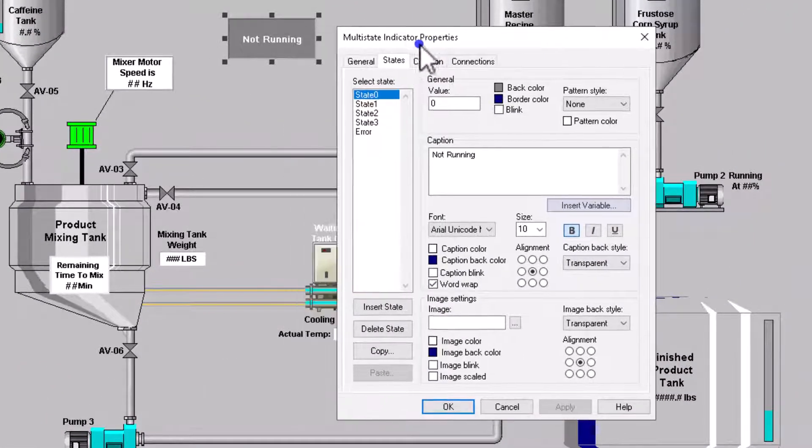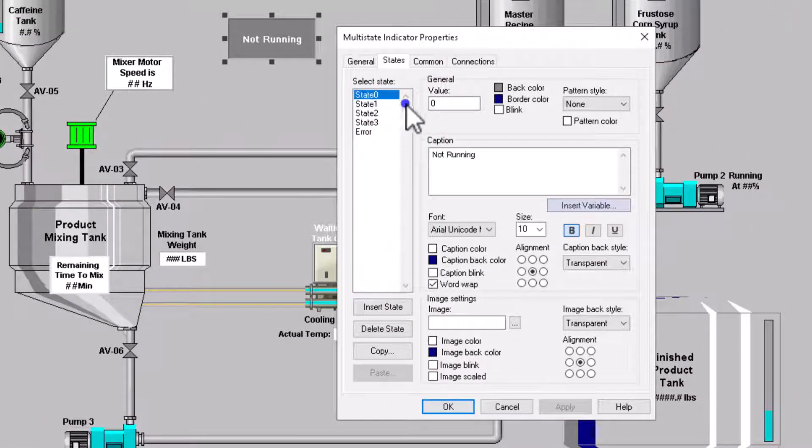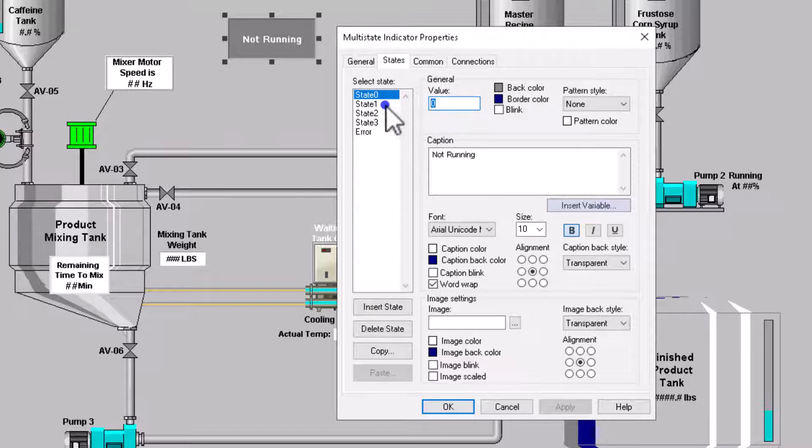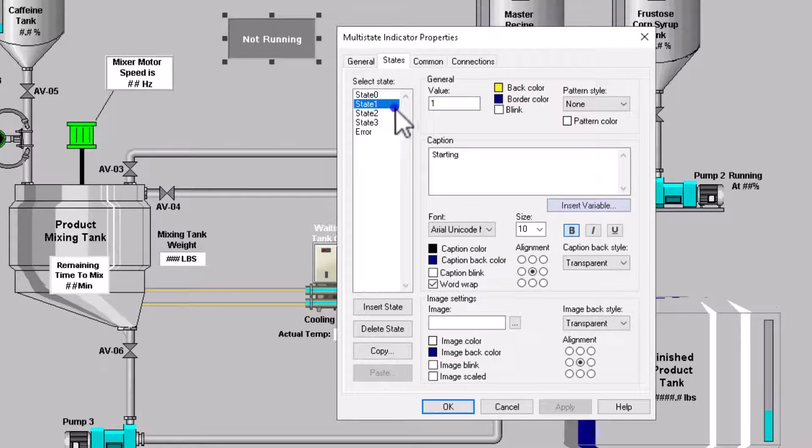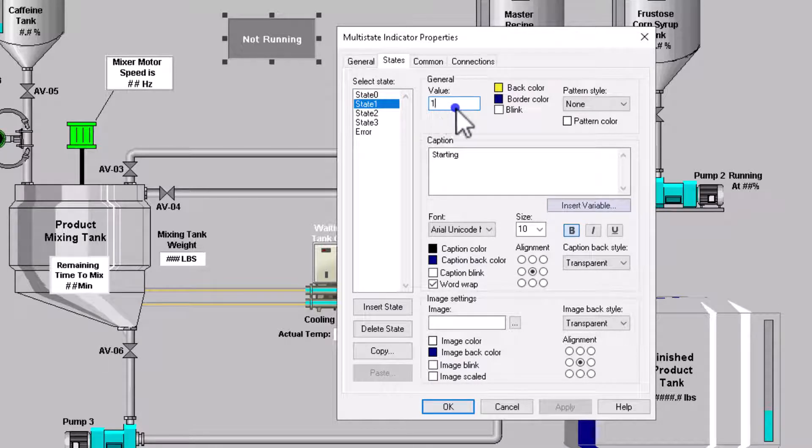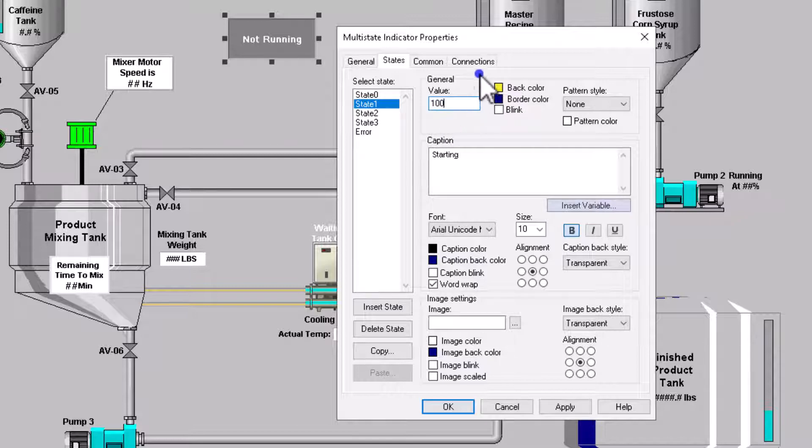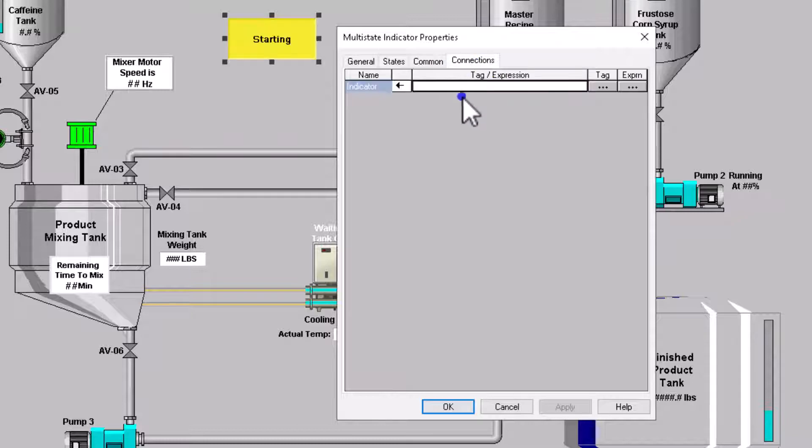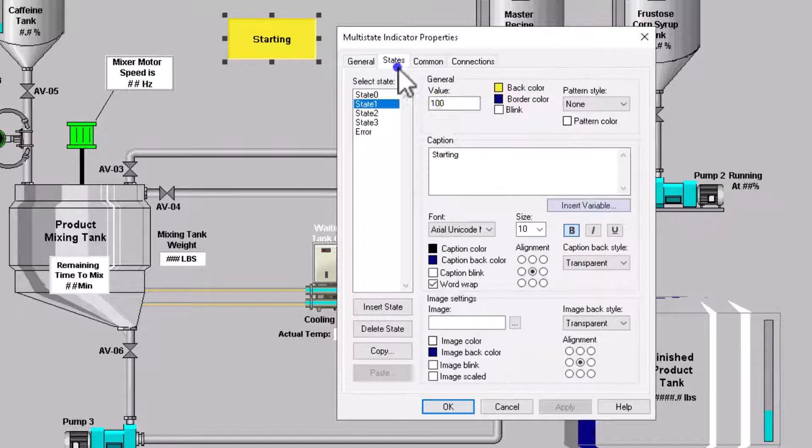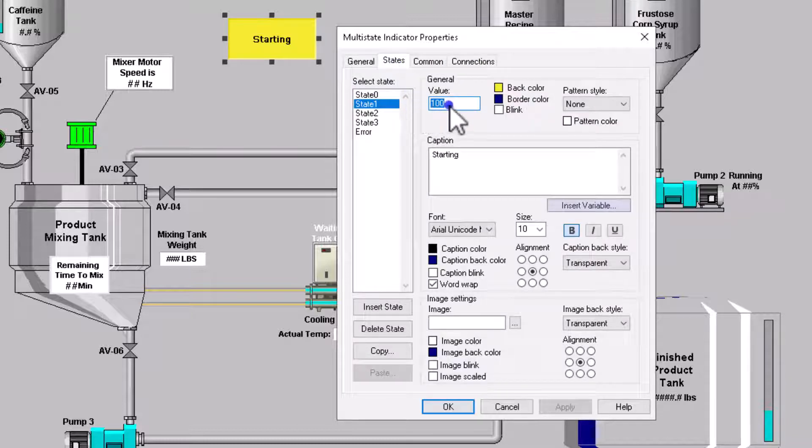when it comes down to it and just keep in mind when you're doing a multi-state indicator, another little quick tip too, is the states do not have to equal the state that you're currently in, like if I wanted to be in this very top one and it's zero. One, if I want, if this was equal to, again, 100, value of 100, right? So whatever the tag I put in here, if it's equal to 100, then that's when that state would pop up.